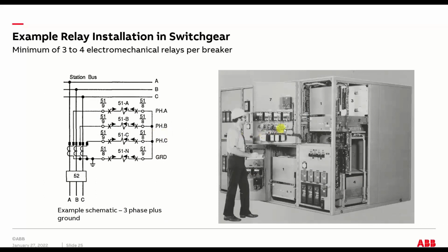Here's an example of what I was talking about before, where you have multiple relays required for the protection of a single circuit breaker. This was pretty typical. This is old GE gear, I think Power Break, so these are probably GE relays too, circa 1980 probably. You can see a three-line diagram here of this one breaker, with pretty much the most basic overcurrent protection you can put on it: 3 relays for phase overcurrent and 1 relay for ground overcurrent. So 4 relays in total, with all the associated wiring, just for one breaker.